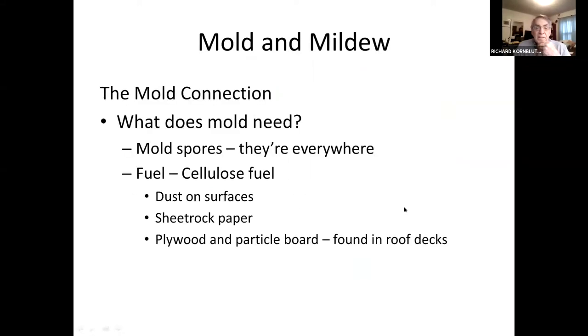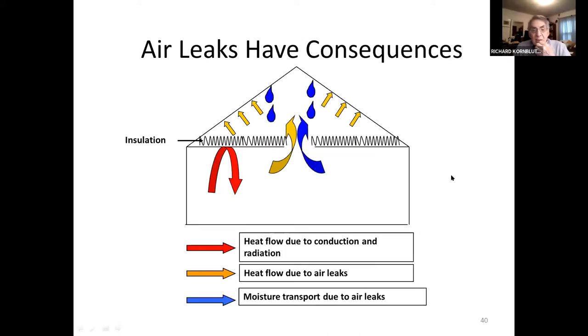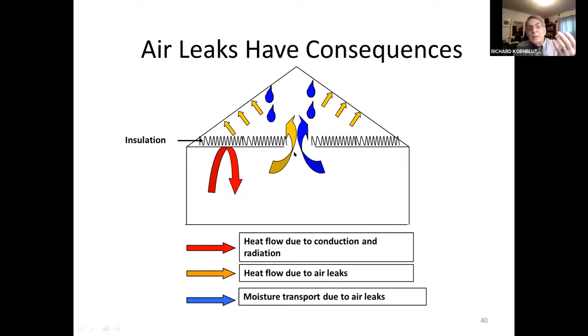So what does mold need? It needs spores, a fuel — which could be dust, drywall paper, plywood, or particle board — and it needs moisture. Air leaks have consequences. The blue represents moisture, the red represents heat, and the orange represents heat flow due to air leaks. Insulation may stop heat transfer by conduction and radiation, but holes at the top of your building will let warm air and moisture transport get to the attic.